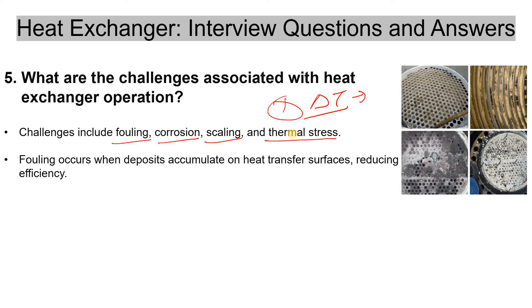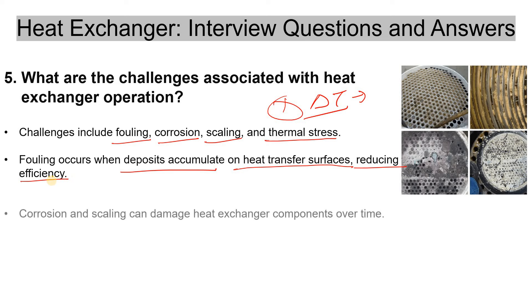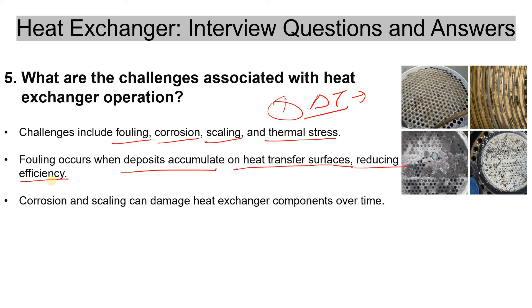Fouling occurs when deposits accumulate on heat transfer surfaces, reducing efficiency — which is why we do hydro jetting or back washing. Corrosion and scaling can damage heat exchanger components over time, which is why we include a corrosion allowance during design, and address scaling through hydro jetting and chemical cleaning.